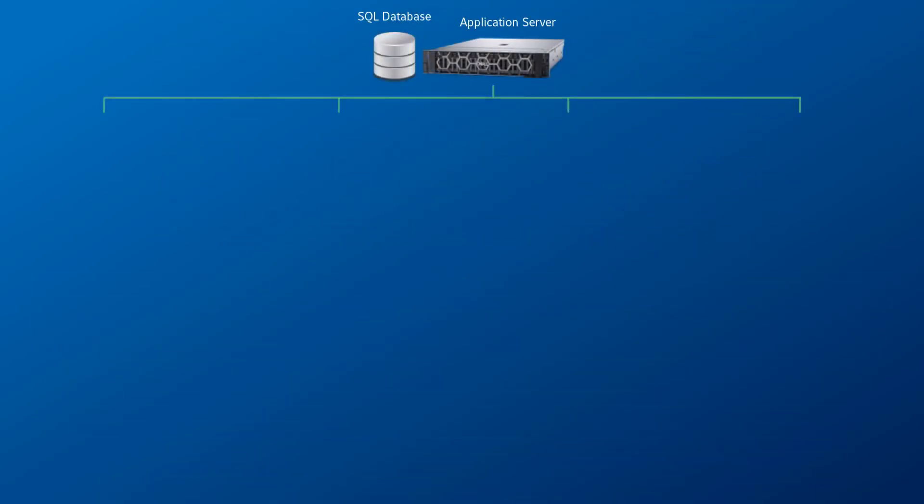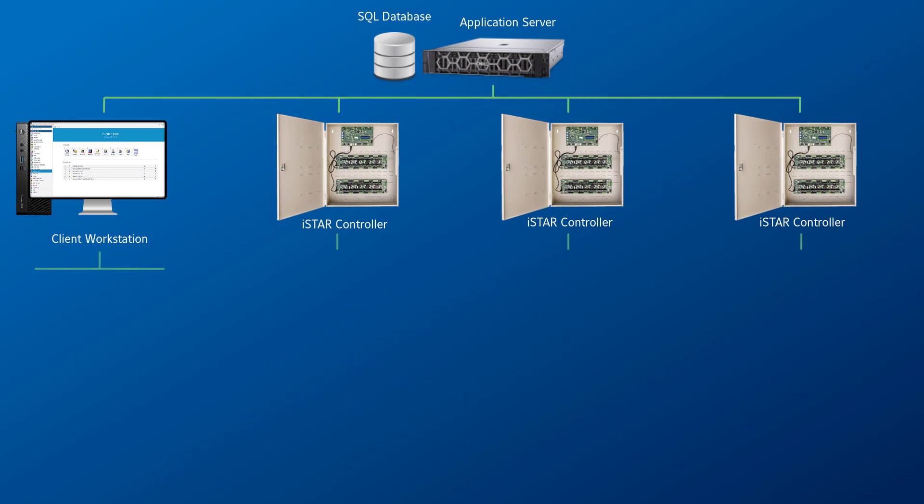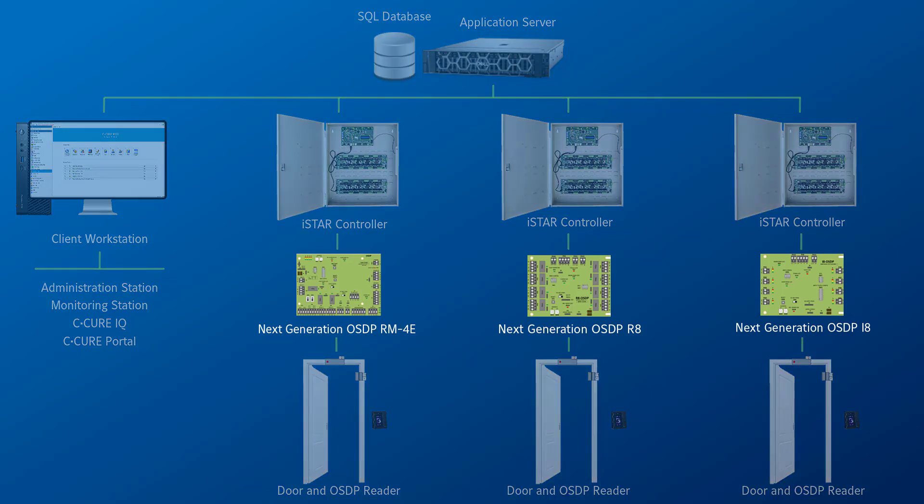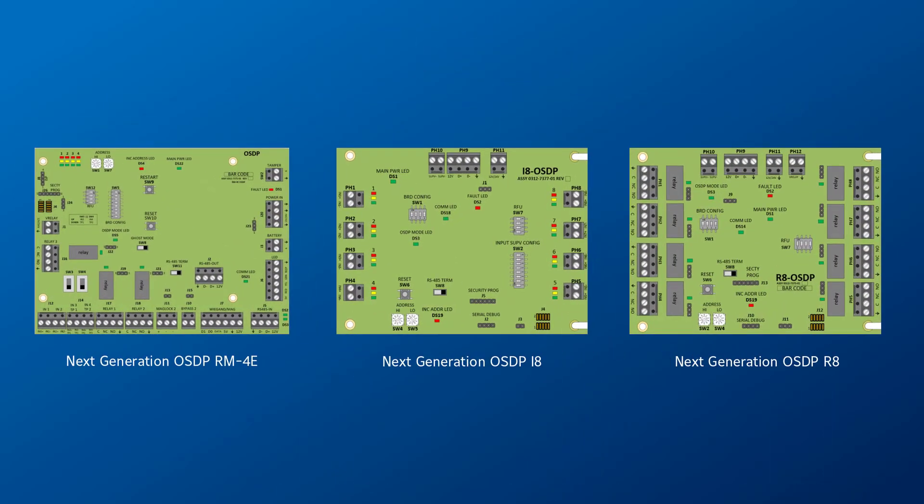To support the use of OSDP, Johnson Controls have created modules and configured C-CURE 9000 version 3003 to support their use. The modules supported by C•CURE include the next generation RM4E, i8 and R8 boards. These modules require the iStar controller to be run in firmware 6.9.5 or higher.